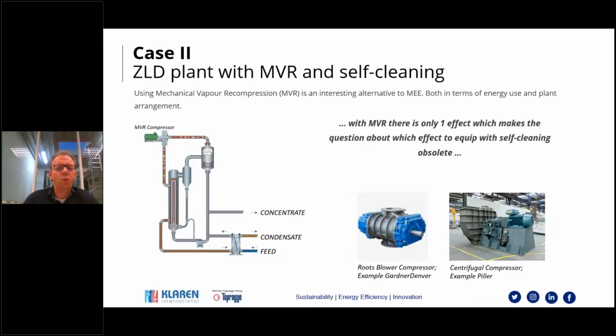Because how does this MVR work? Well, it works on the basis that if you look at the energy consumption of evaporation, it has to do with the heat that you put in to convert a liquid to a vapor, so the latent heat. And this is really taking a lot of energy to evaporate 1 kg of water. So you would like to recover this as much as possible. And that's why in a multi-effect, you use it in more stages. Still, some vapor will go to the condenser.